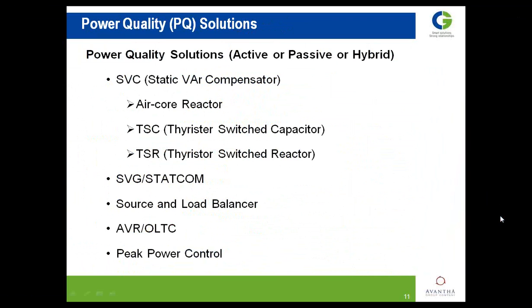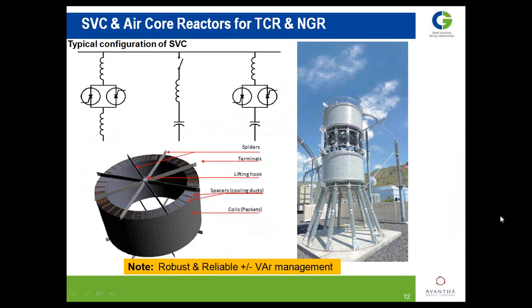And that comes to the SVC with the help of thyristor-controlled capacitor or reactor, for the conventional, or reactor for the air core, which is a new field and getting popular due to its robustness, or SVG, load balancing and unbalancing, which Pannalal tries to cover, or AVR or on-load tap changing and peak power control, which is the latest and new need for all the utilities. This basic is known to most of you, and as Pannalal said, it's robust, reliable, and more about positive and negative power management.